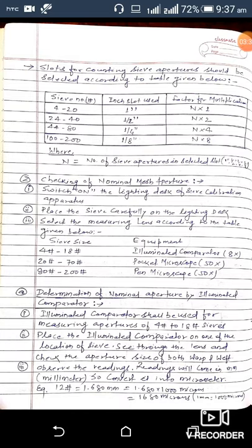The slots for counting sieve apertures should be selected according to the table given below. For sieve number 4 to 20, use the one inch slot and the multiplication factor is n × 1. For 24 to 40 mesh, the half inch slot is used and the multiplication factor is n × 2.